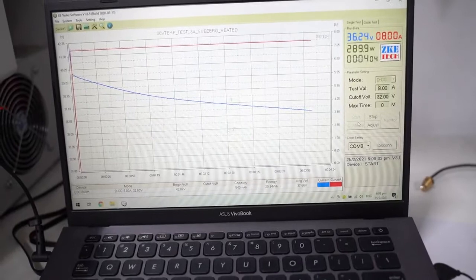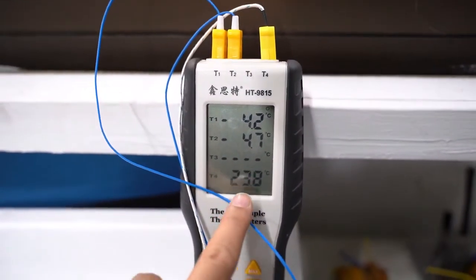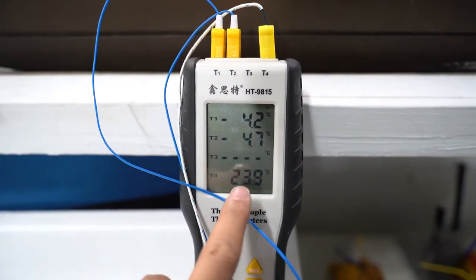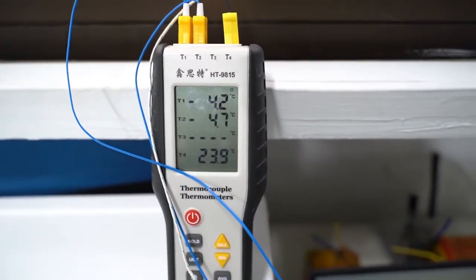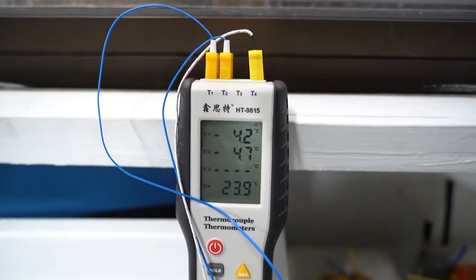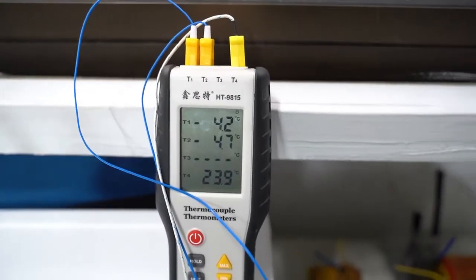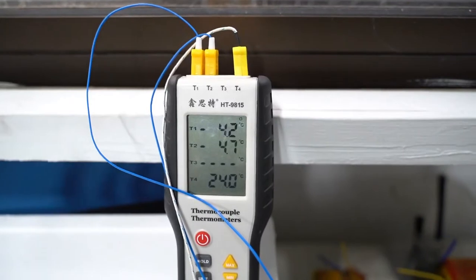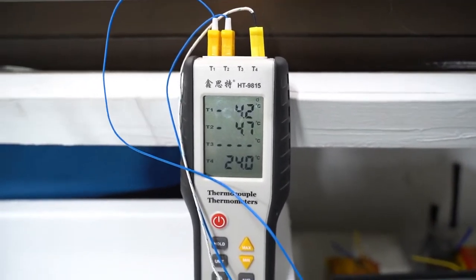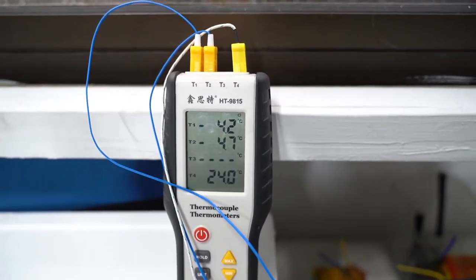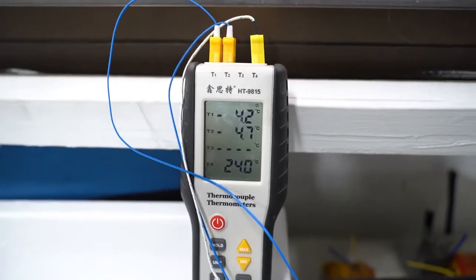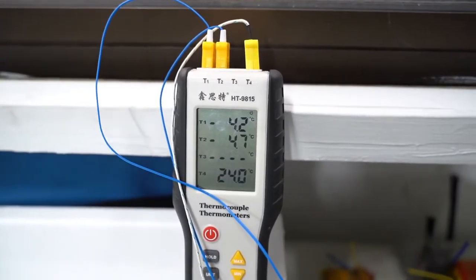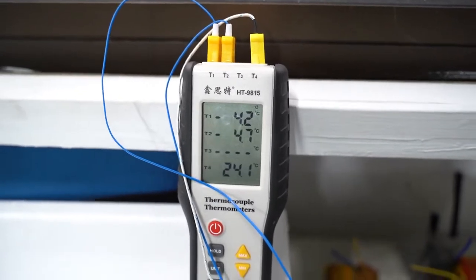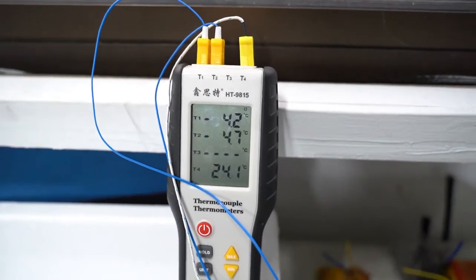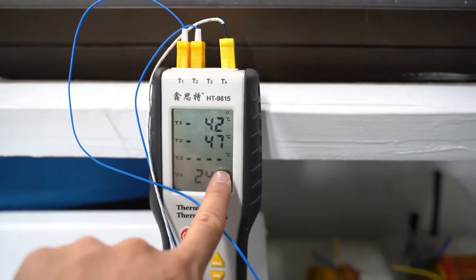Okay, at the 4-minute mark our battery temperature is climbing to about 24 degrees, which is perfect. The heat from the battery discharge is retained within the battery environment, hence warming up the battery itself. This is ideal in winter conditions, where we want to use the battery's heat to warm the battery itself. The outside ambient temperature is still sub-zero.